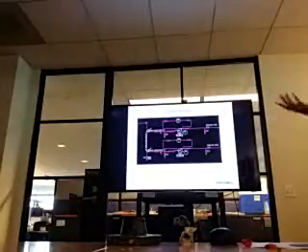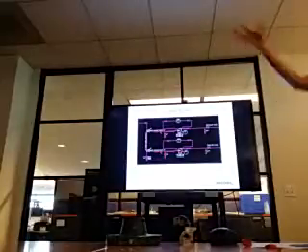So the steam, we always want to keep steam in the line. And what the steam does when it cools down, it becomes condensate. Well, now we have slugs of condensate hanging out with the steam, and the steam's going to be cooled down more. So we're trying to rid the condensate out of the steam as much as possible. When you see a steam line, you'll see some drops, and there's some drip legs or dirt legs, trying to get rid of any of the condensate, to keep just live steam in that main. Well, the problem is when you drop the condensate, you're also going to have a little bit of steam in there too, and you don't want to discharge any live steam downstream to a drain.